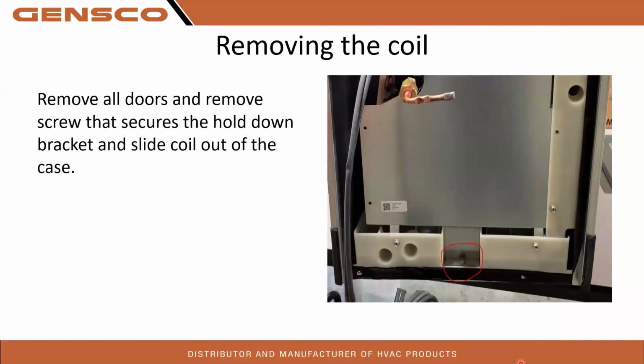To remove the coil, you'll take the front door off, and then this bracket right down here that I have circled has a single screw in it. Take that screw out, the mounting bracket comes off the coil, and that's the only thing that holds the coil in, so it will slide out at that point.